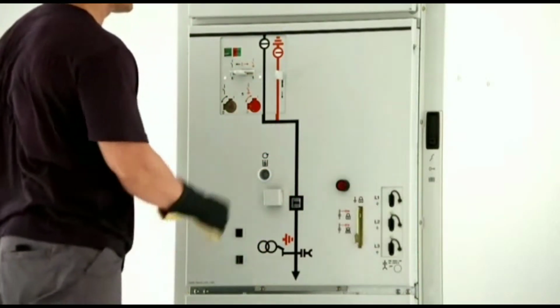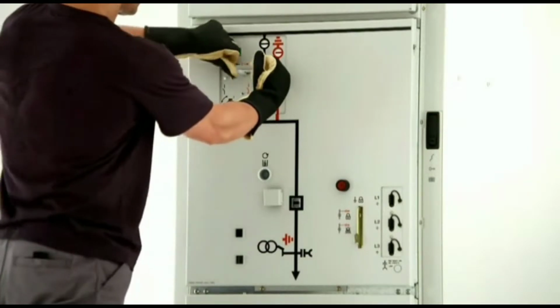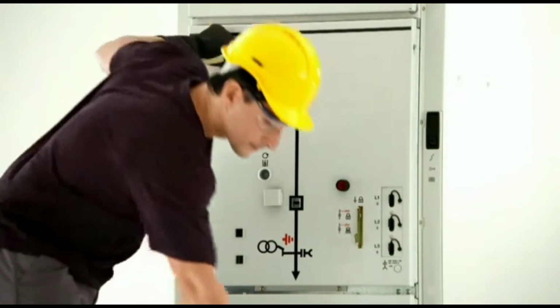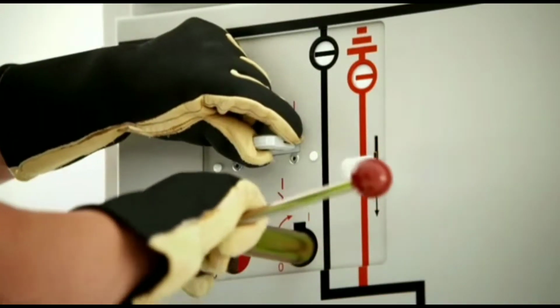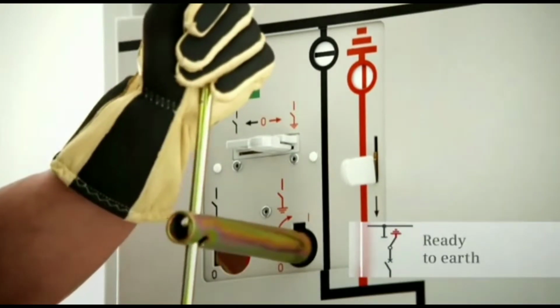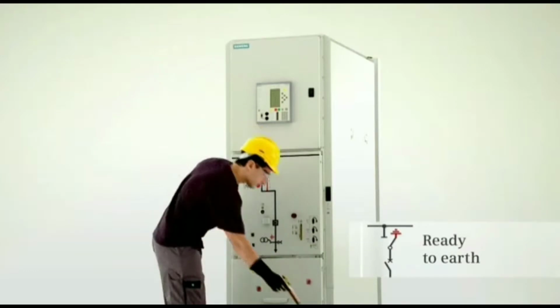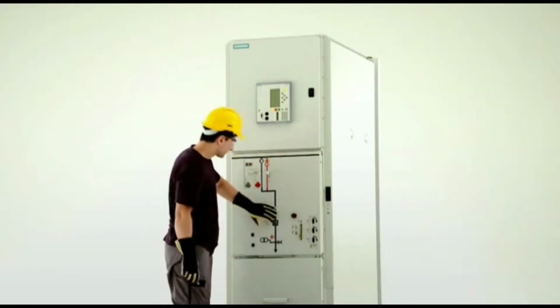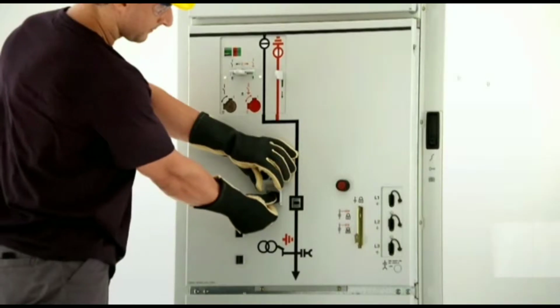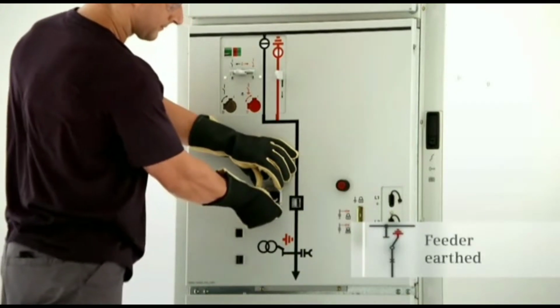The interlocking lever is now pushed down again and the control gate is pushed to the right to unlock the actuating opening for ready to earth. Turning the operating lever clockwise switches the three-position disconnector to the ready-to-earth position. The feeder is earthed by closing the circuit breaker.